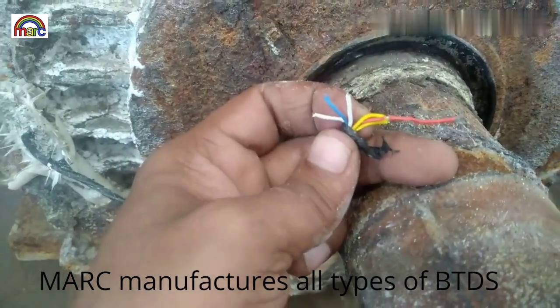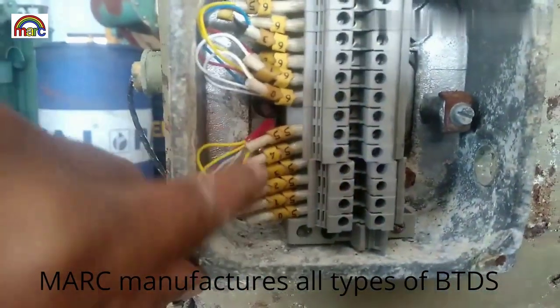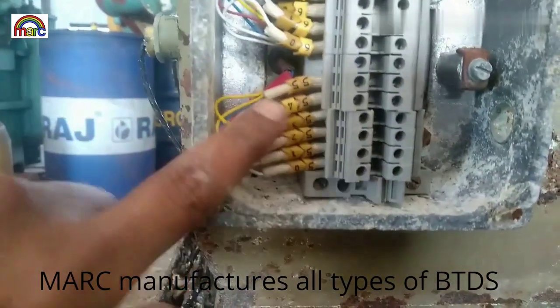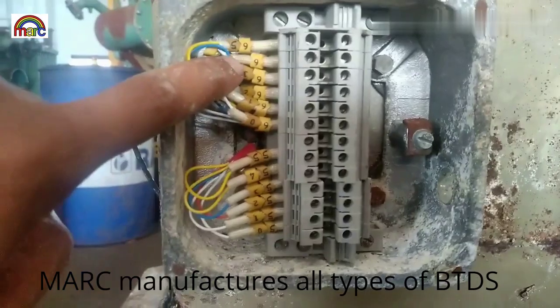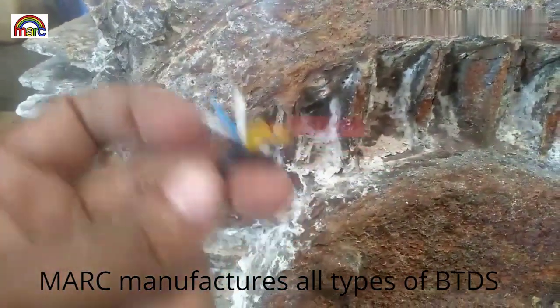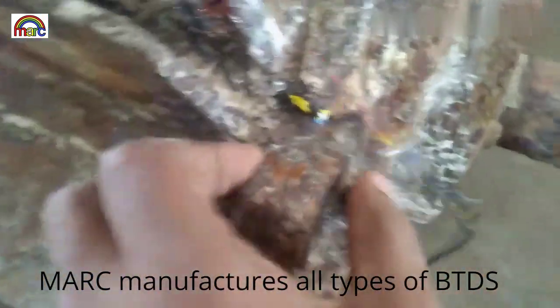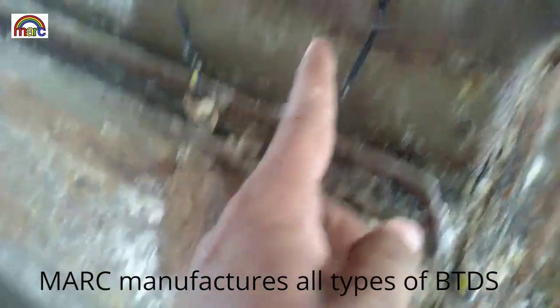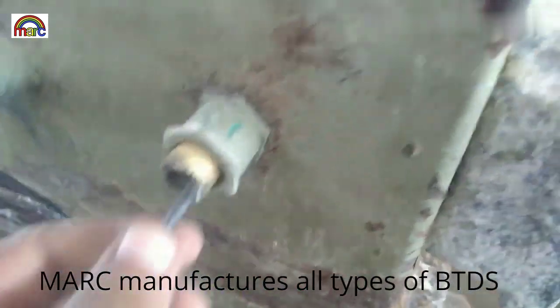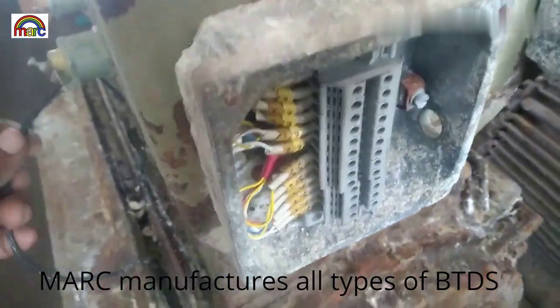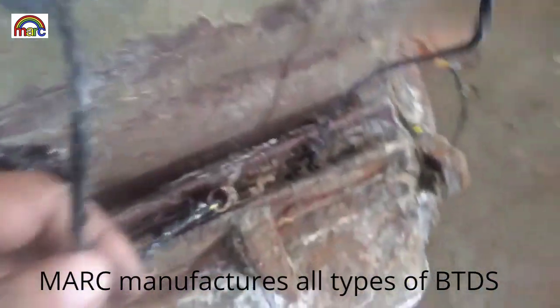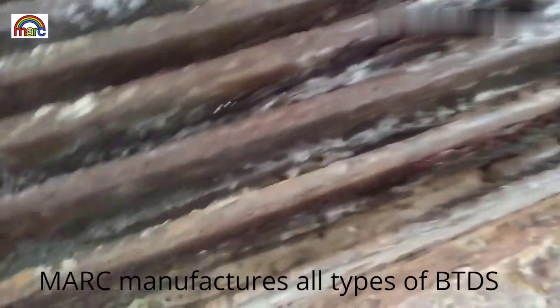The temperature detected on the probe is taken to the BTD box, where all the wires are connected, and from this box all wires are connected to your metering circuit. Normally there are many kinds of BTDs, 3 wire, 6 wire. Every rotating machine has two bearings and accordingly two BTDs, one at the drive hand side and the other at the non-drive hand side. Now let's see the non-drive hand side BTD.